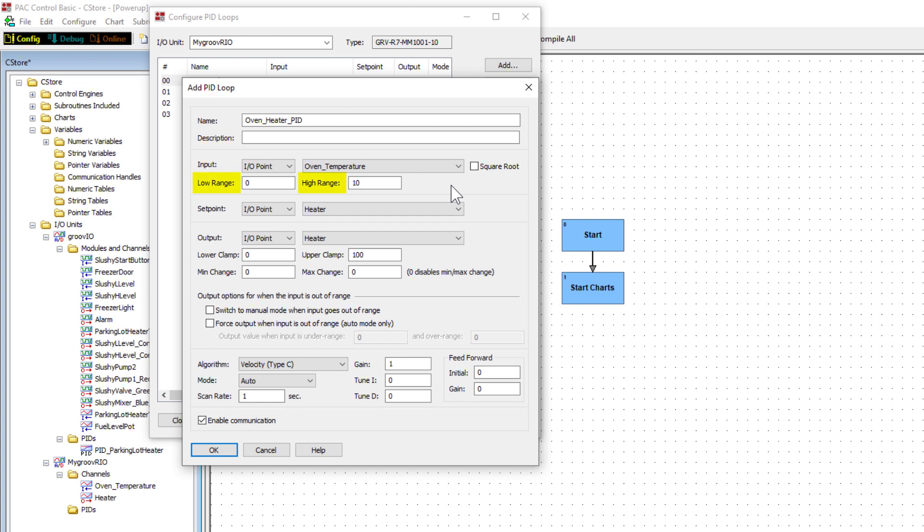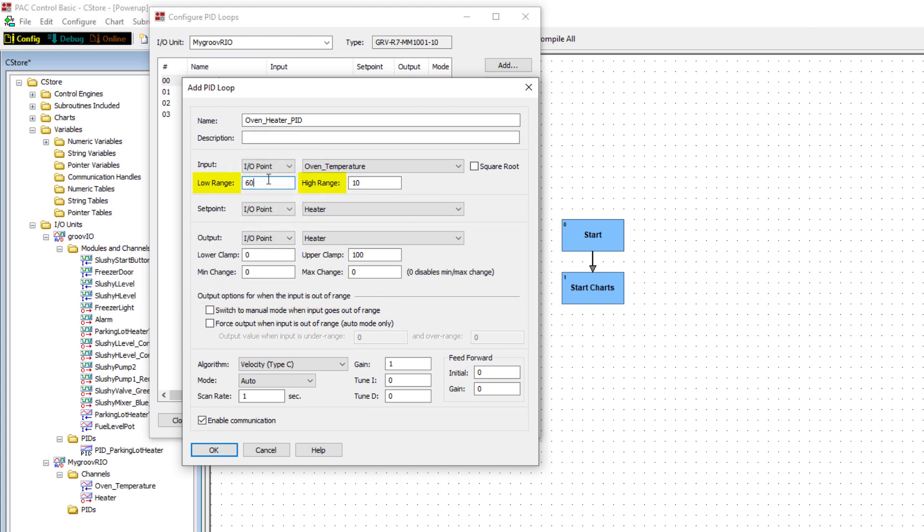We won't check square root in this case. Low range and high range set a valid range for your input. You'll notice here that a default range was entered on this unit. If the input is out of range, we'll indicate what to do a little later in these configuration settings. I'll set up the low range to 60 and the high range to 90.